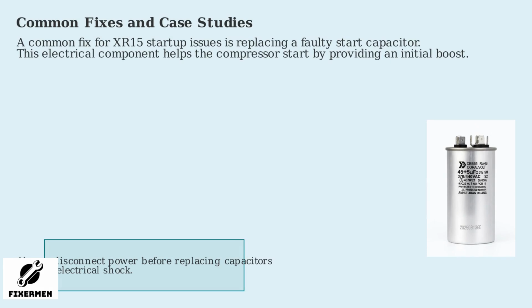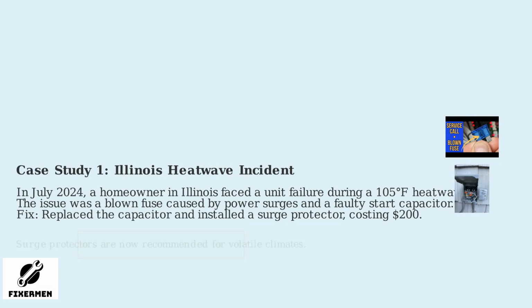A common fix for Trane XR15 startup issues is replacing a faulty start capacitor. This electrical component provides the initial boost needed for the compressor to start. According to industry data, capacitors account for about 40% of startup failures in these units. For example, in July 2024, a homeowner in Illinois experienced unit failure during a 105 degrees Fahrenheit heat wave. The root cause was a blown fuse from power surges, compounded by a faulty start capacitor.